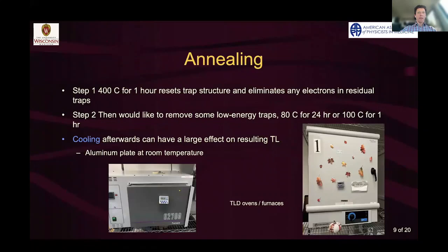After you've sorted them and irradiated them, then you have to anneal them. That involves an oven or a furnace. First, you need to reset the traps at 400 degrees C for an hour. Then we like to heat them lower and slower for another 24 hours to remove some of those low energy traps, which makes the readings more accurate later. And then cooling actually has a large effect on the TLDs. We like to put them on an aluminum plate at room temperature.